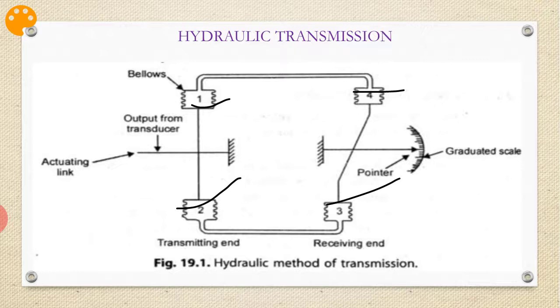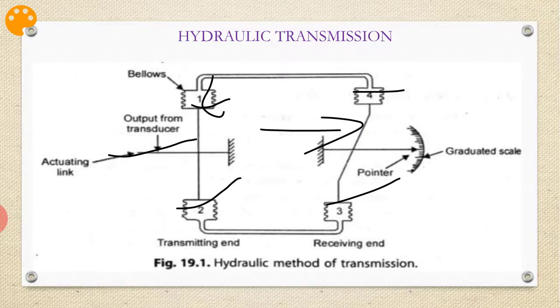When the actuating link at the transmitting end is operated by the measuring element, one bellow expands and the other is compressed. This expansion and contraction is communicated to the receiving end, which moves the receiving pointer by an equal amount. The purpose of using two bellows on either side is to compensate for changes in ambient temperature.